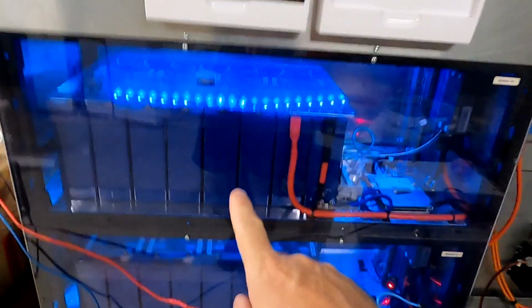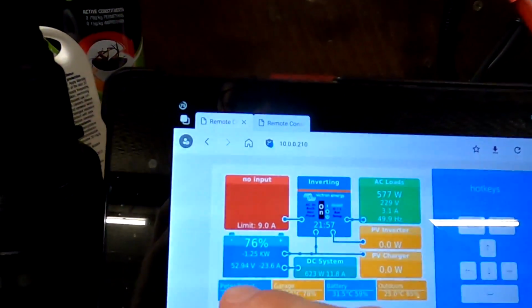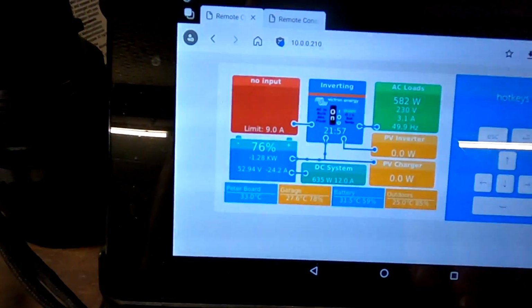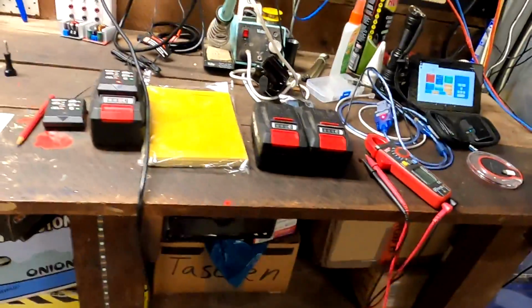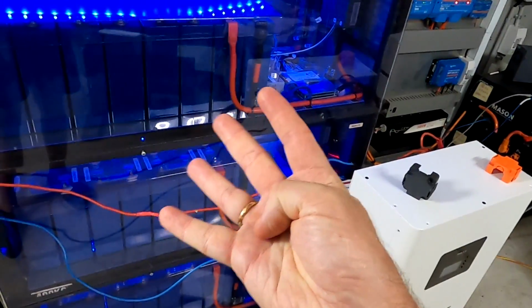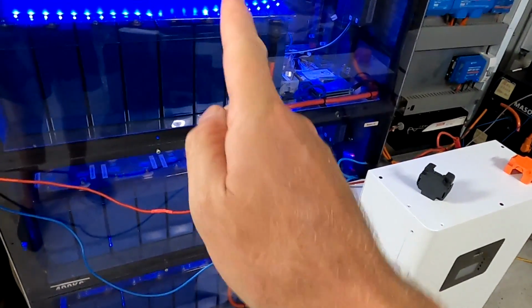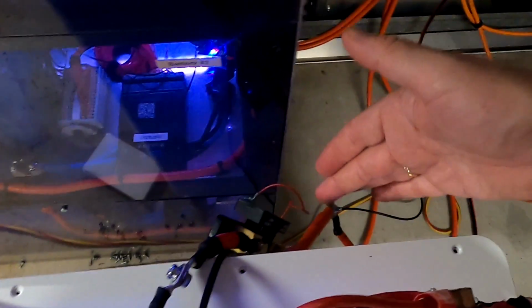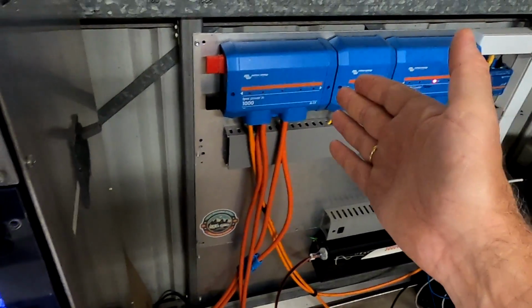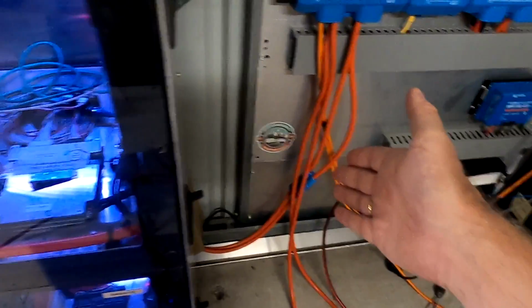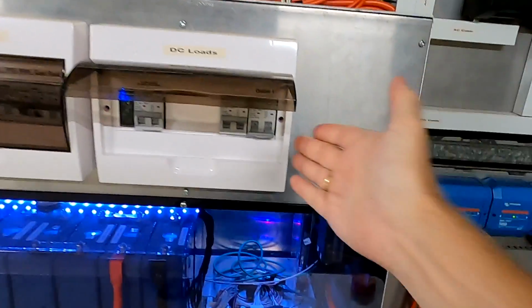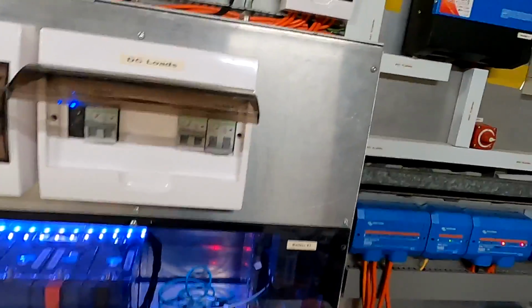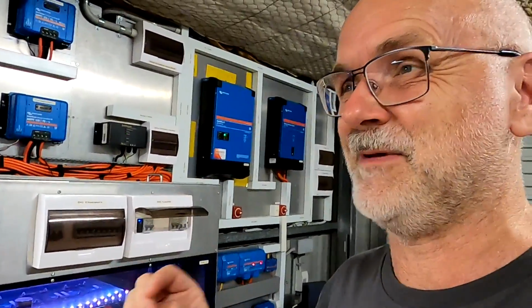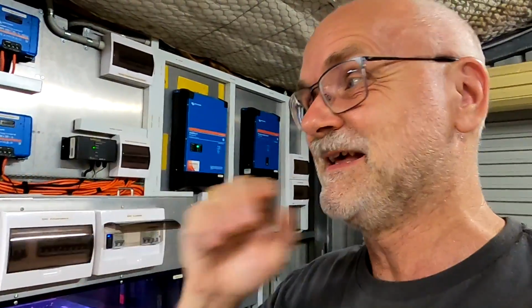We've got 52, almost 53 volts in these batteries, and close to 50 volts in this battery. So there's a 3 volt difference, and there will be a lot of current flowing. Of course we've got some cabling: a smart shunt, different connections, the Powerwall 2.0, an Anderson connector in between, cables in the top compartment to the circuit breaker and back to the main bus bar system. So there's a bit of resistance here with the cabling, and I hope this is enough to limit the current.